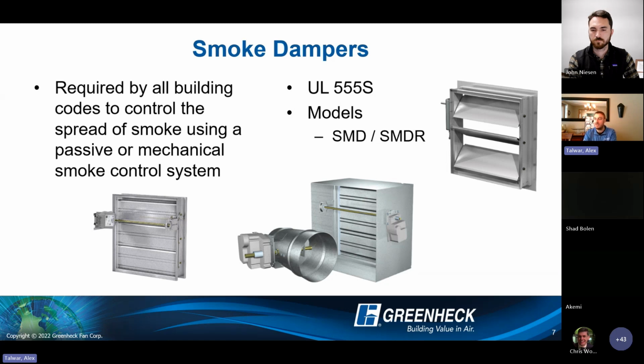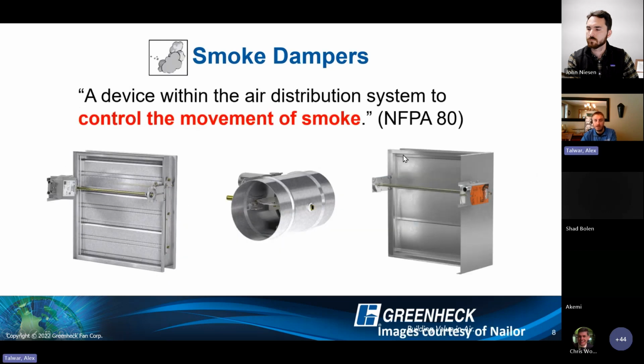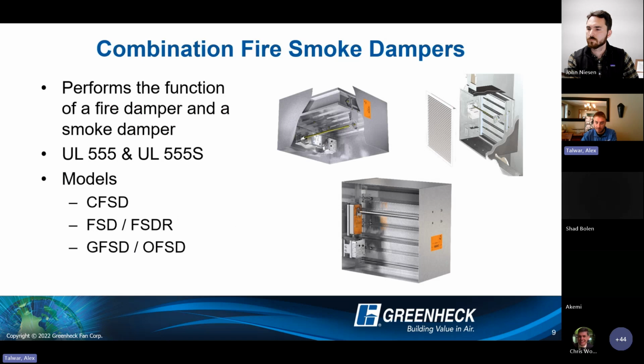Smoke dampers have a similar purpose, except instead of preventing the spread of flame, now we're talking about limiting leakage when they close and preventing the spread of smoke throughout a system. So a slightly different purpose, obviously different requirements, different features on the products. We'll see seals along the blade edges and the edge of the frame to help seal up when they are closed and prevent that spread of smoke when it's pressurized against a closed damper. They have their own separate test standard, UL 555S, and for us, pretty simple: SMD smoke damper models, or SMDR. NFPA 80 defines it as control of the movement of smoke.